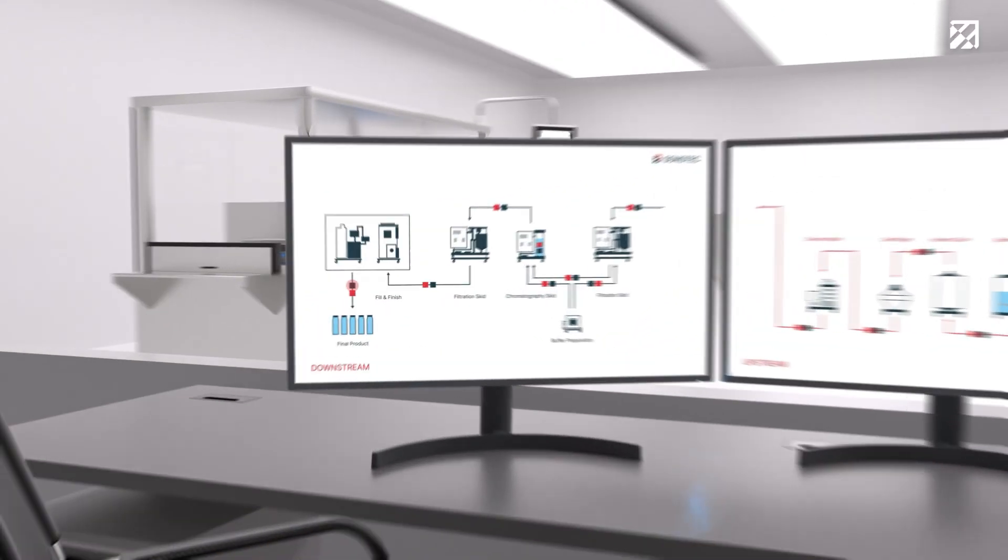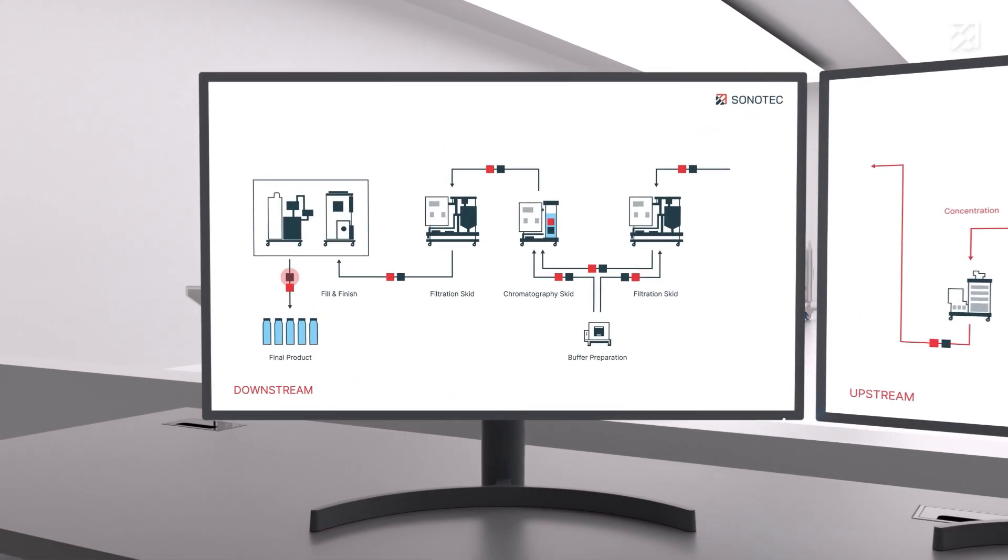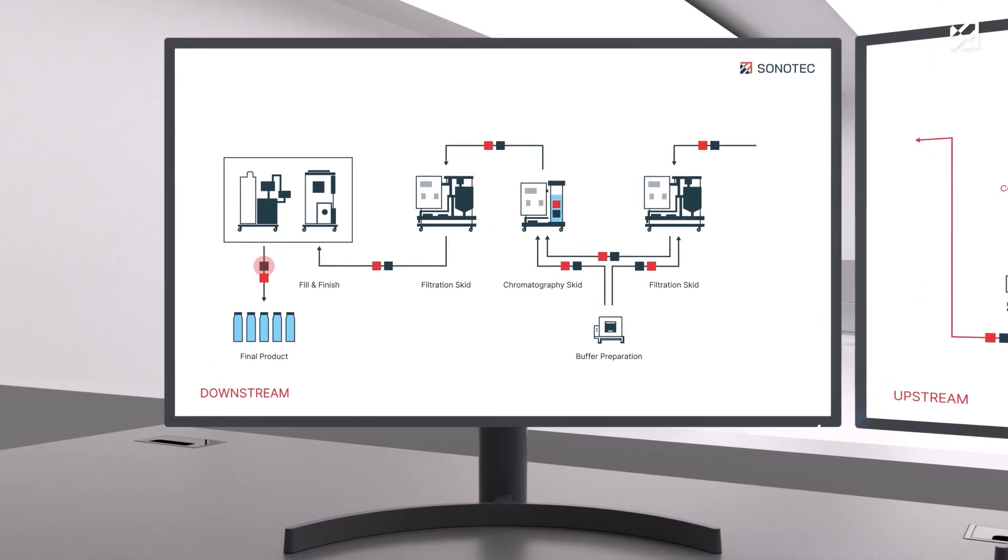Based on the ultrasonic transmission principle, we detect air bubbles reliably and in real time to allow immediate action when an air bubble occurs.